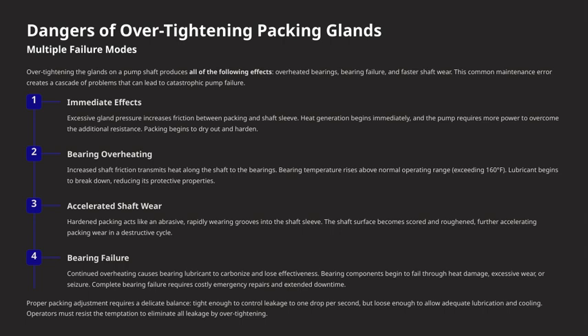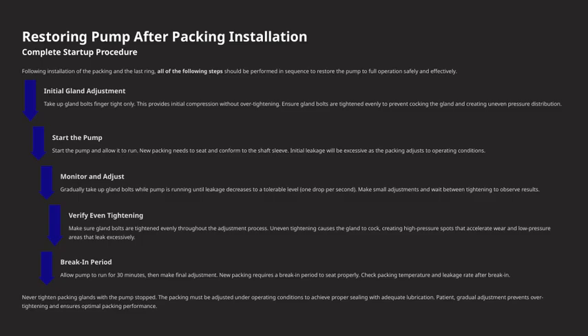It's a delicate balance, tight enough to control leakage to about 1 drop per second, but not so tight that it hampers lubrication and cooling. It's essential for operators to resist the temptation to tighten excessively in an attempt to eliminate all leakage, because doing so can cause these serious problems we've discussed. Now, let's walk through the steps for restoring a pump after installing the packing and the last ring.